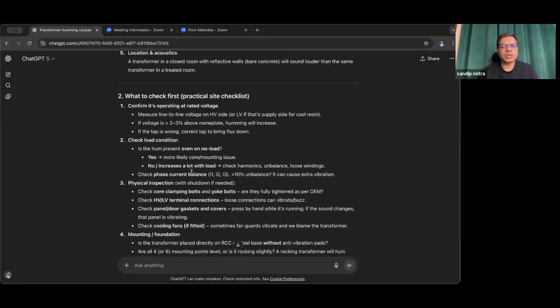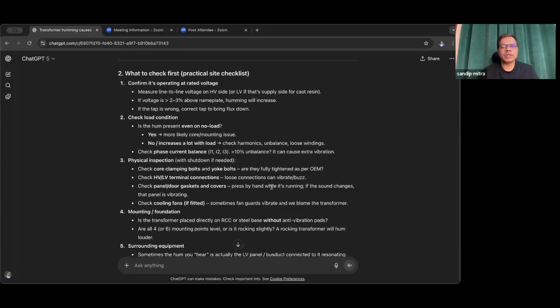Check the load condition. Is the hum present even at no load? If yes, it is more likely a core or mounting issue. If no, or if it increases a lot with load, check harmonics, unbalance, and loose windings. Check phase current balance. If there is greater than 10% unbalance, it can cause extra vibration. And do a physical inspection with shutdown if needed. After shutdown, check core clamping bolts and yoke bolts. Are they fully tightened as per OEM?